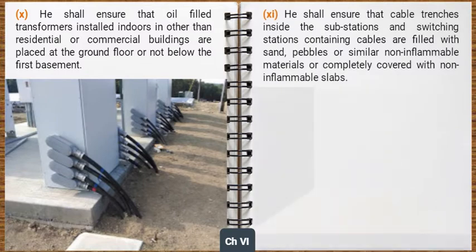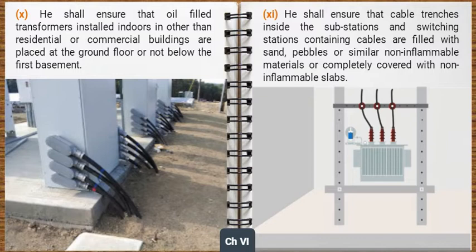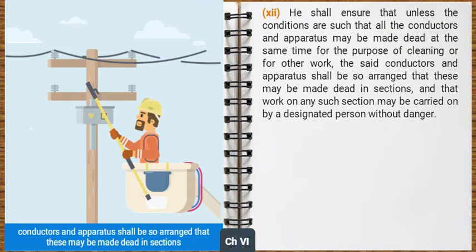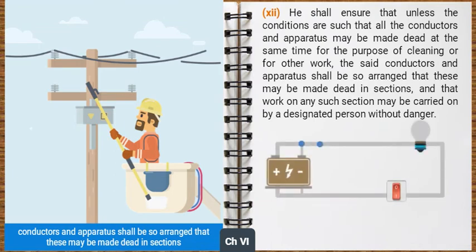He shall ensure that cable trenches inside the substations and switching stations containing cables are filled with sand, pebbles, or similar non-inflammable materials, or completely covered with non-inflammable slabs. He shall ensure that unless the conditions are such that all the conductors and apparatus may be made dead at the same time for the purpose of cleaning or for other work, the said conductors and apparatus shall be so arranged that these may be made dead in sections and that work on any such section may be carried on by a designated person without danger.